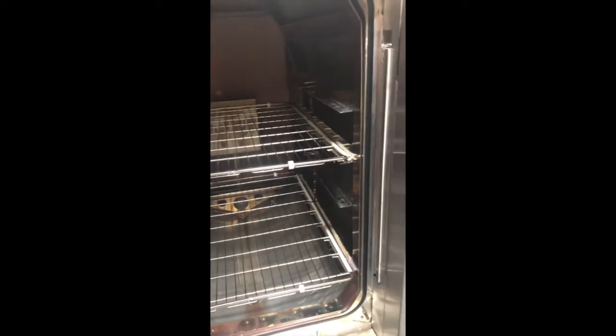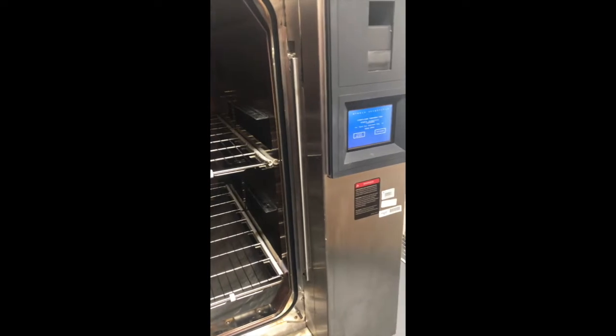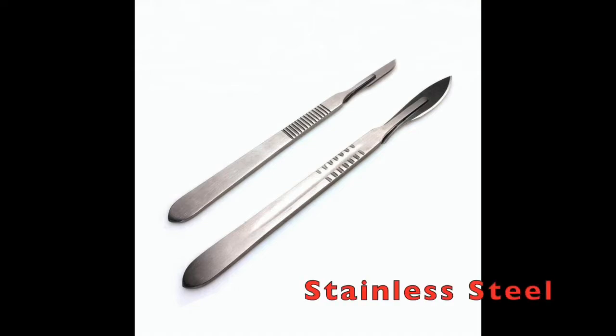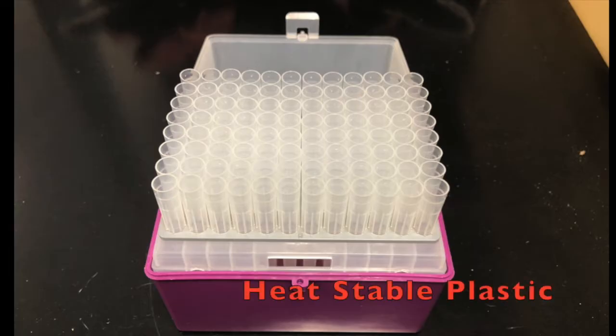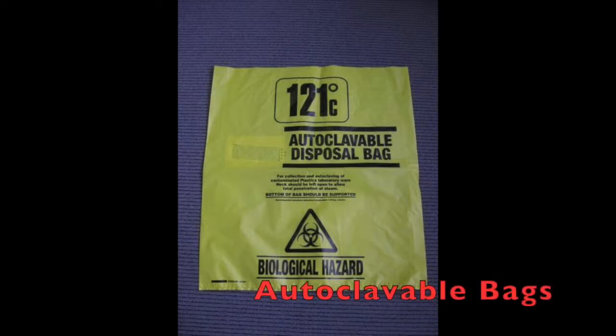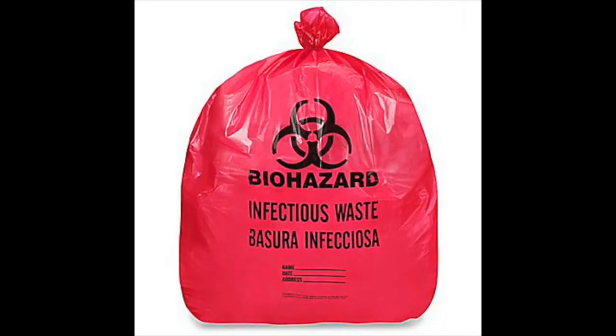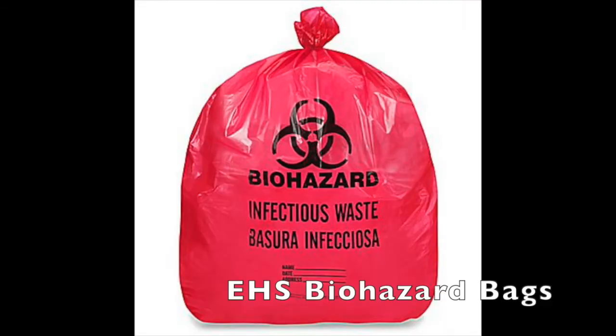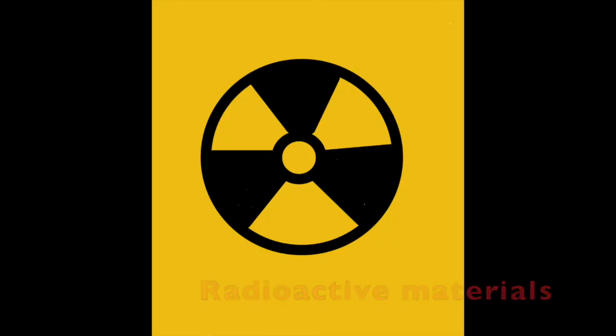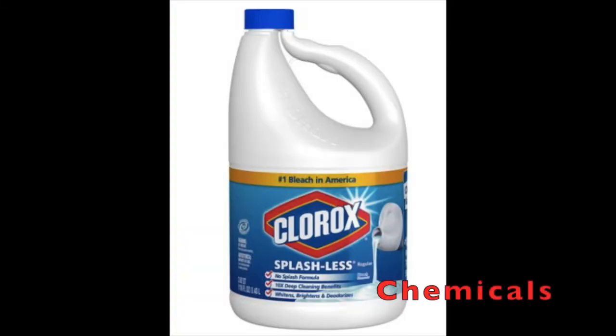An autoclave can either rely on gravity displacement or it can have a vacuum pump. It is safe to autoclave any stainless steel equipment, glass without cracks, heat-stable plastics, and any autoclavable bags. It is unsafe to autoclave the biohazard bags provided by EHS, any material that is radioactive, and chemicals, especially bleach, flammable materials, and acids or bases.